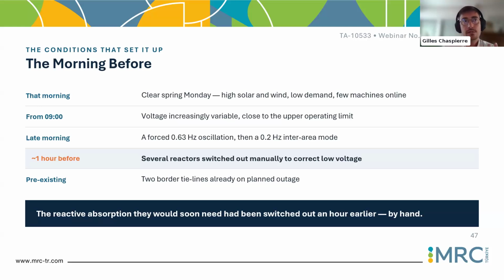So a shunt reactor is a very simple asset able to absorb reactive power, so very useful in terms of over-voltage. But unfortunately, in the guidelines, when they see this inter-area mode, they are anticipating a risk of low voltage because of oscillations. The voltage oscillates, so at some point it can reach a low value. And to anticipate that, they manually switch out shunt reactors. And so you understand that the pre-existing conditions were the worst possible. A lightly loaded grid, and on top of that, they are disconnecting reactors, which means we are further reducing the reactive power margin, and the voltage is rising again.